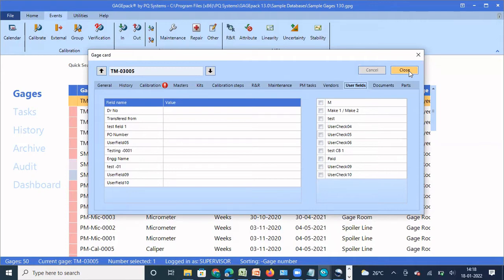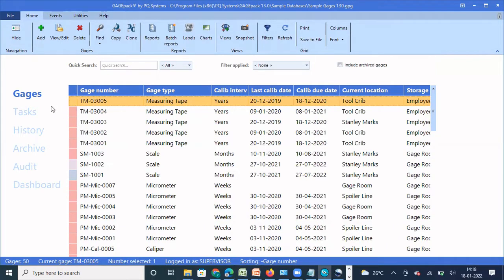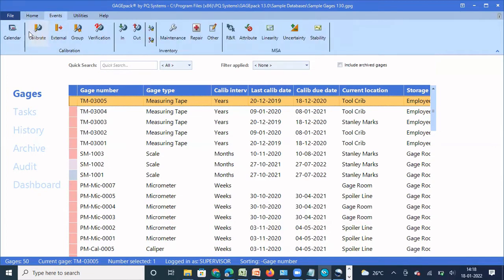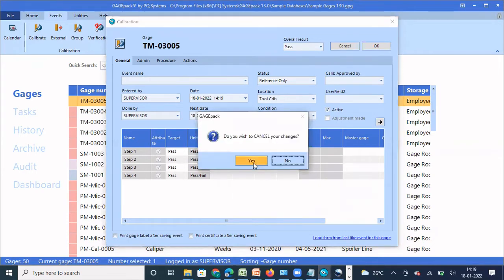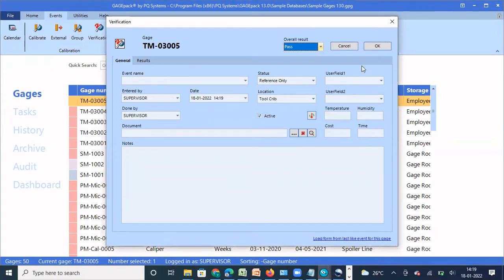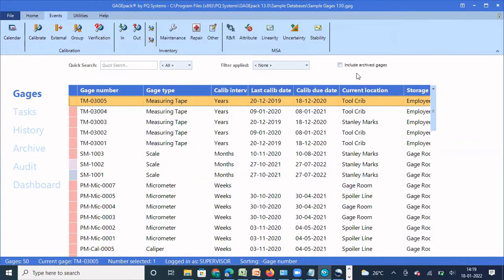This is how you update fields on the general gauge card. Similarly, you can do the same in Events. I've highlighted a gauge and clicked on Event - there are different event types: calibration event, external calibration, group calibration, verification event, check-in, check-out, group check-in, group check-out. If I select a calibration event, in calibration you also have two user fields available. For example, User Field One was already renamed to 'Calibration Approved By', and there is also User Field Two.